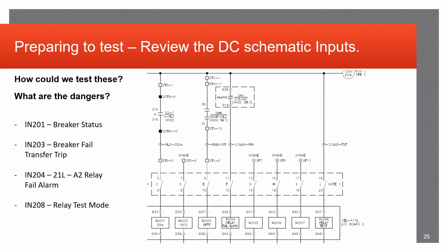Because if the breaker is closed, but the relay thinks it's open, then the protection is not going to be enabled because there's nothing to worry about. The breaker's open. Whereas if a fault were to occur and the relay doesn't identify that the breaker is in fact closed and that there is a fault, nothing will happen, and the breaker and other equipment could be immensely damaged.